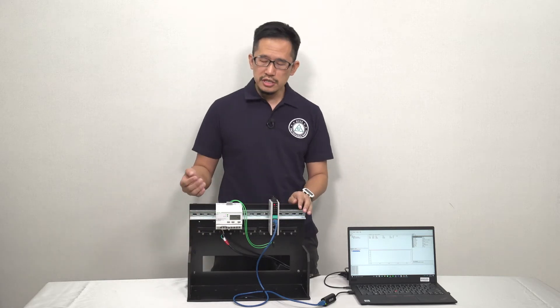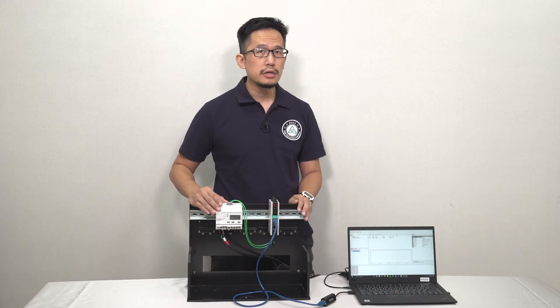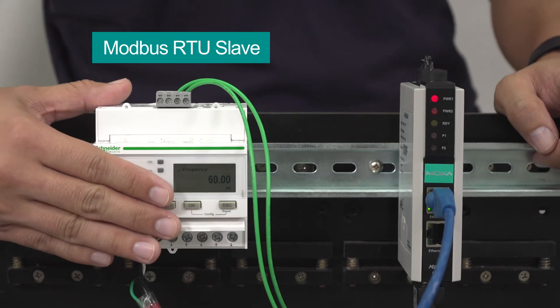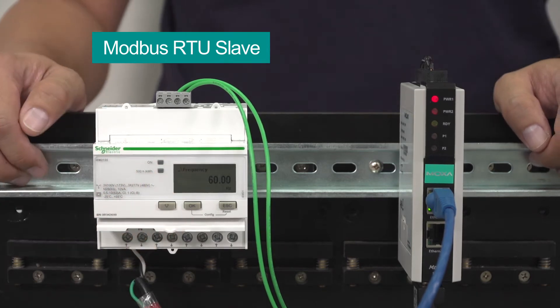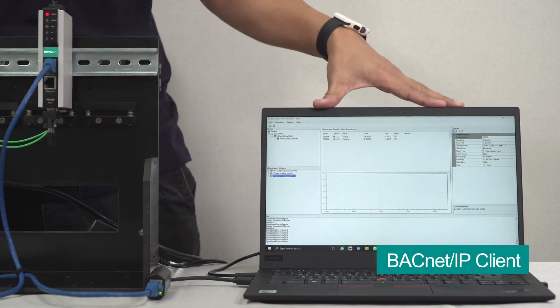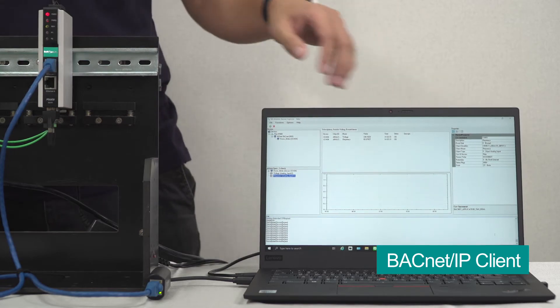To connect this power meter to our BACnet IP network, we have to convert Modbus RTU protocol, which the power meter uses, to BACnet IP protocol, which our BACnet IP client uses.